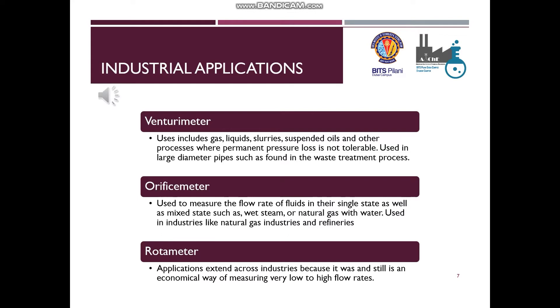Let us talk about the industrial applications of flow measuring devices. Venturimeters are used for gas, liquids, slurries, suspended oils, and other processes where permanent pressure loss is not tolerable. They are also used in large diameter pipes such as those in wastewater treatment. Orifice meters are used to measure flow rates of fluids in single and mixed states such as wet steam or natural gas with water, and are common in natural gas industries and refineries. Rotameters are widely used across industries as an economical way of measuring very low to high flow rates.